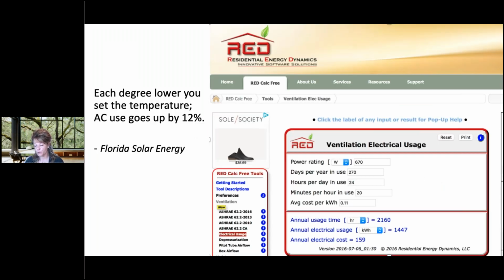So a lot of times we get questions like: if I'm building a very energy efficient, tight home, and now I have to add another piece of equipment, don't dehumidifiers use a lot of energy? And the reality is they're very effective and energy efficient at controlling the moisture. And if you can set that thermostat higher, because you are more comfortable when you control the relative humidity, 85, 90 degrees in Florida is very different than 85, 90 degrees in Arizona. Oftentimes it's not the heat, it's the humidity, right?